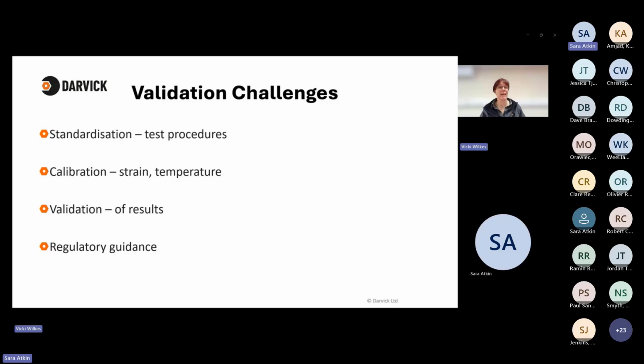There's also issues around calibration. So load calibration is okay. Load cells can be outside of the chamber. Pressure sensor validation, you can put those elsewhere in the system. They don't have to be subject to the extreme temperatures. But strain measurement, people want to do strain control testing. At the moment, to our knowledge, there is no actual calibration of extensometers in the very cryogenic temperatures and in the different atmospheres. And there is no UKAS accredited thermocouple calibration below liquid nitrogen temperatures, so below -196.